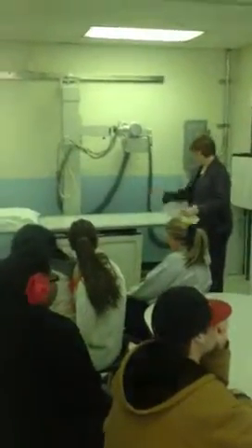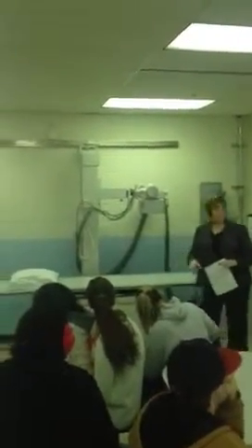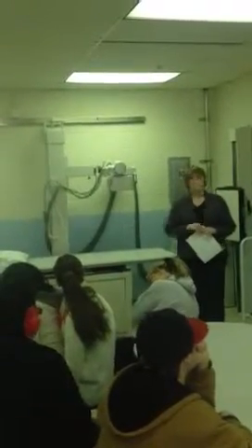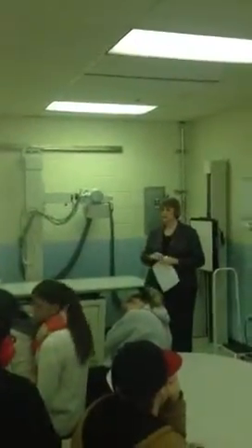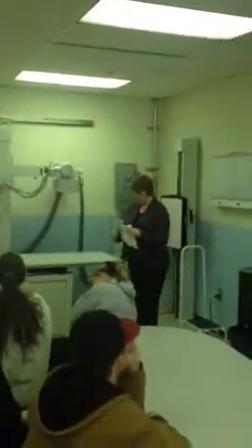Okay. So the floor, is it a primary barrier or secondary? Actually both, but it's definitely always a primary barrier because it's the most common primary barrier you have. So the use factor for the floor, for a primary barrier, is going to be what? 1. Okay, what about the ceiling for use factor? 0, because you're not going to direct a beam at the ceiling. Are you going to direct a beam at the control booth? Never. How many times should it scatter? 2. Yeah, twice before it hits the control booth.